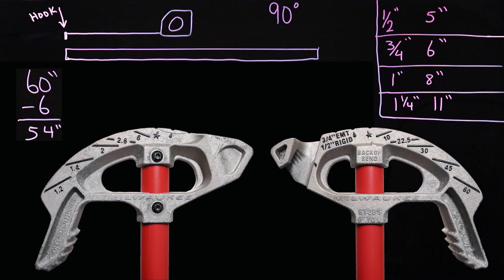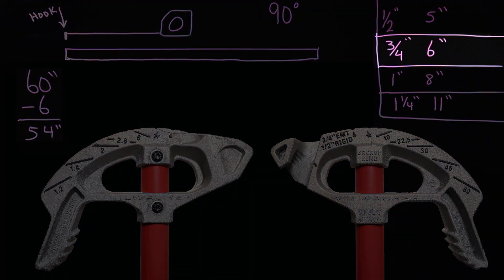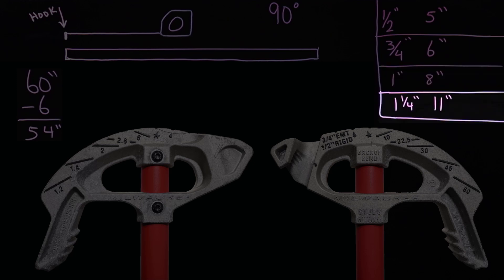Deduct from your tape, from your measurement, six inch for three-quarter, eight inch for one inch, 11 inch for inch and a quarter.